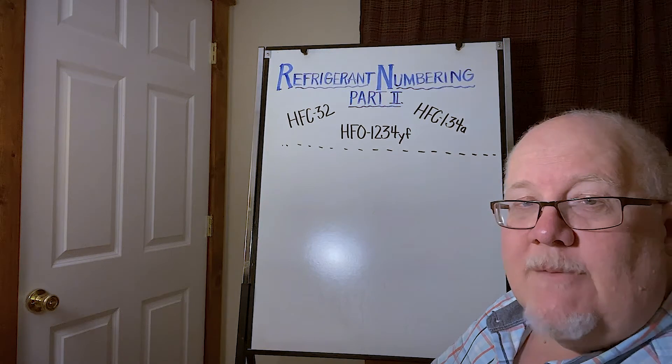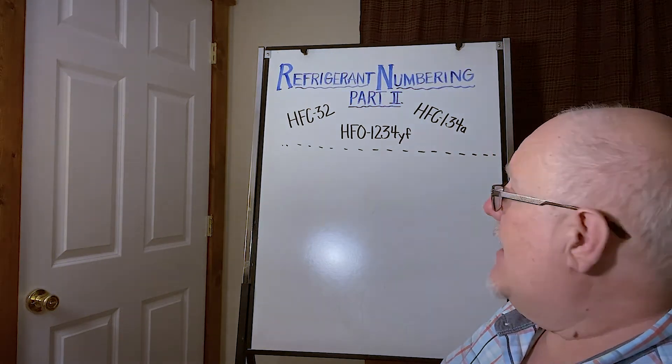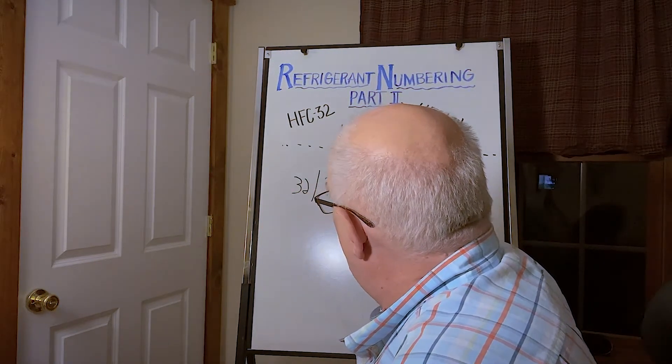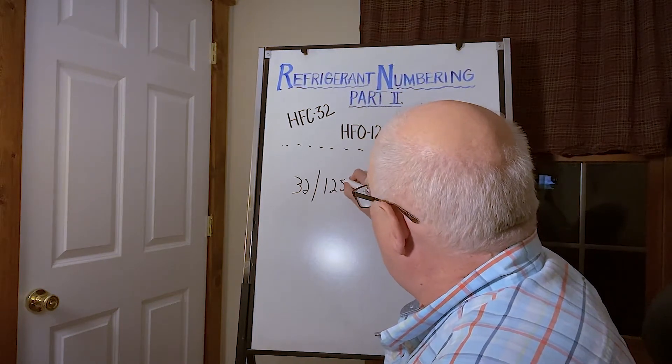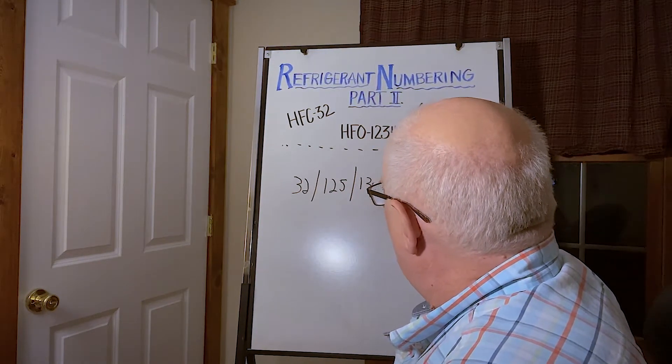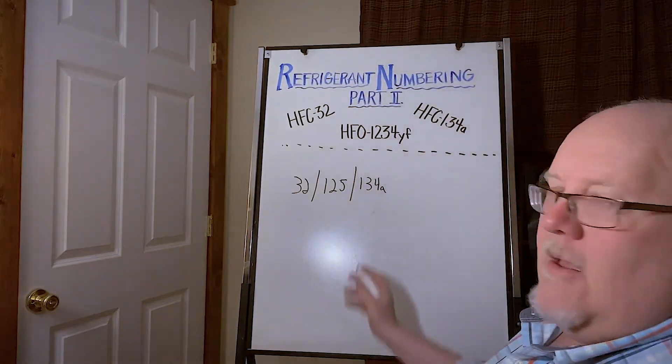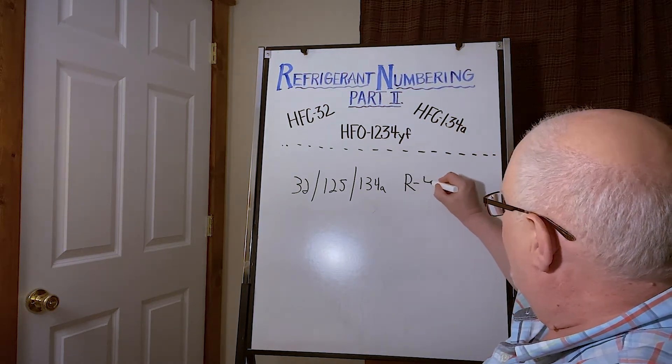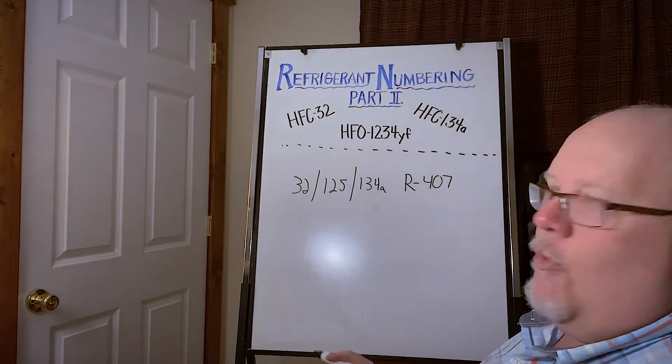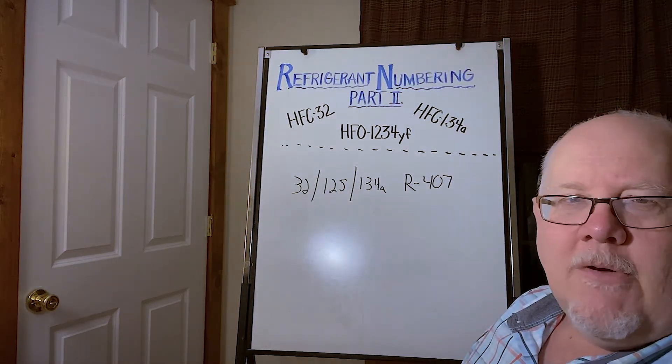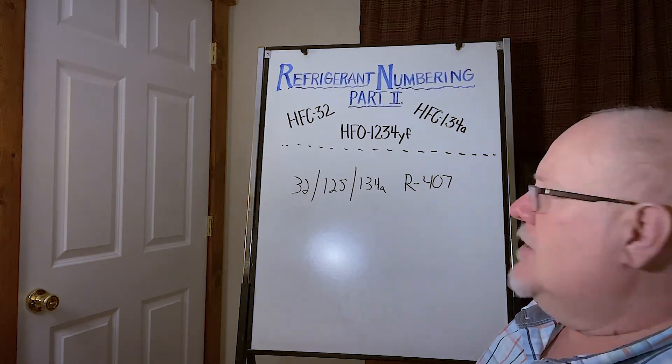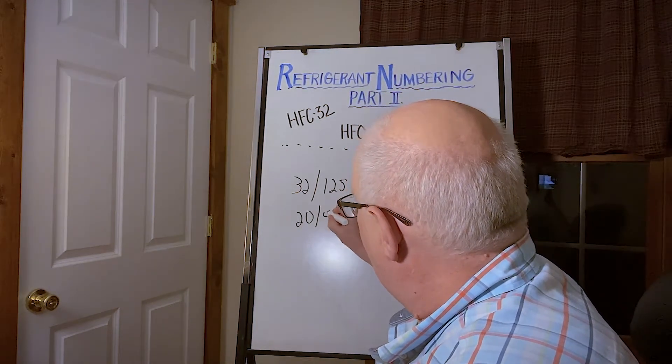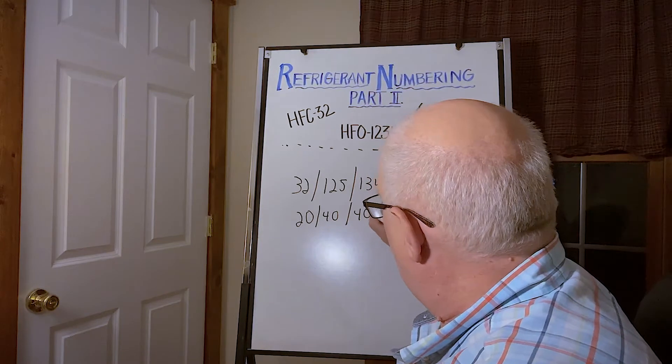So for instance, let me give you an example, something widely used. If we were to make a blend of three components, say HFC-32, HFC-125, and HFC-134A, that formula was assigned an R number of R407 when the first combination of those three components was presented. So it happened to be that those were put together in a composition of 20, 40, 40 percent.